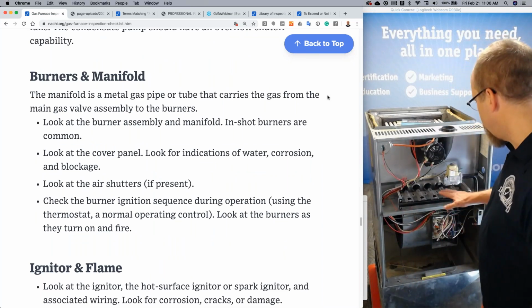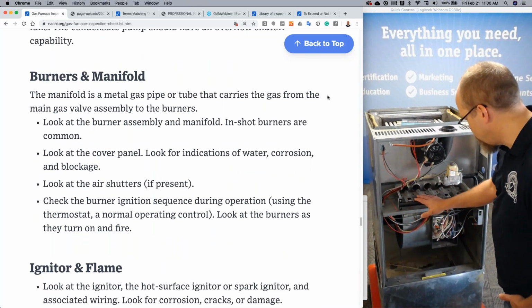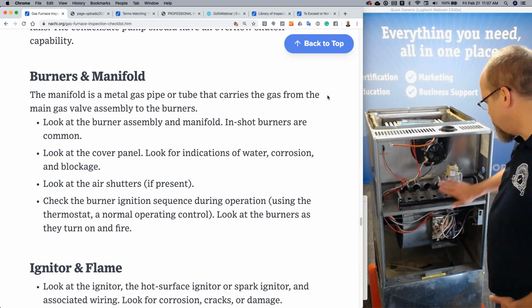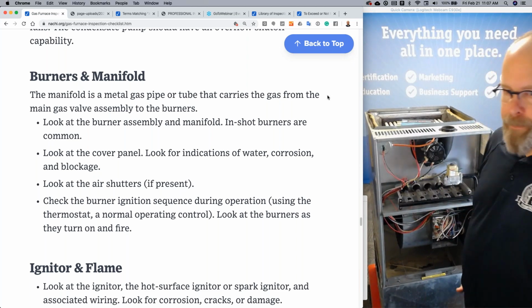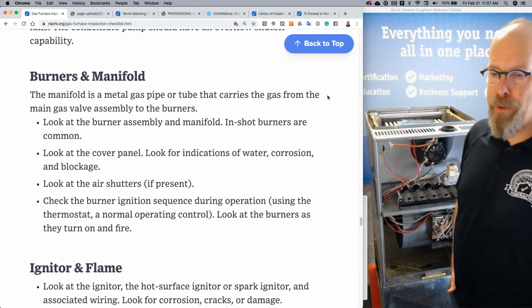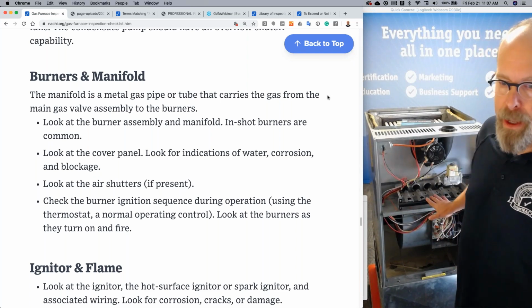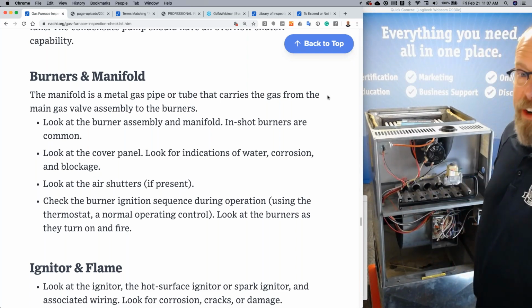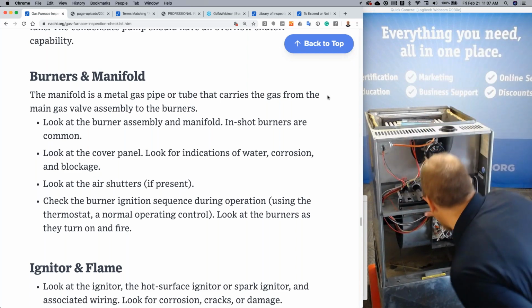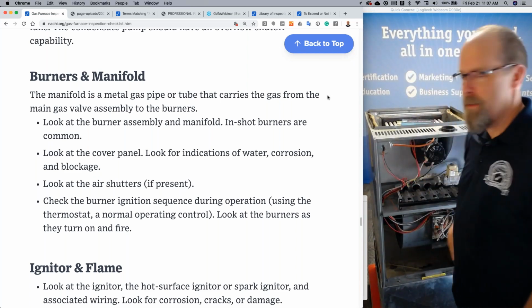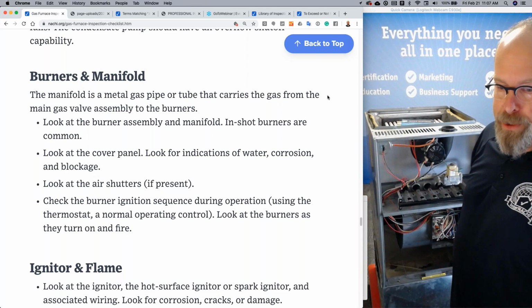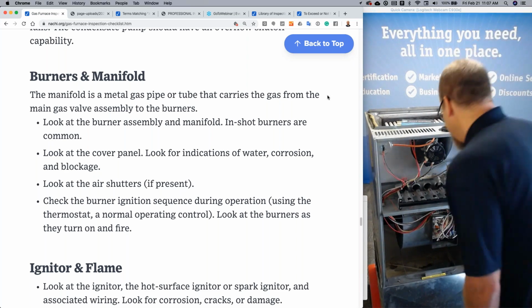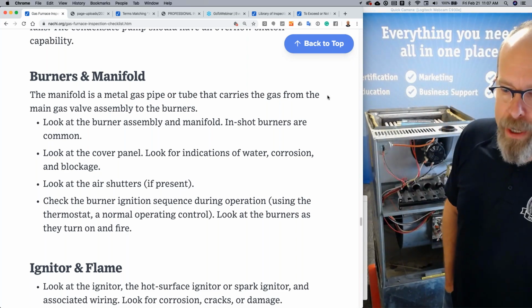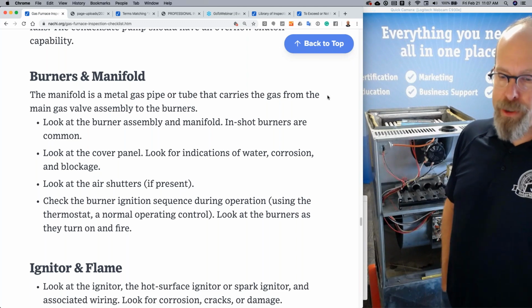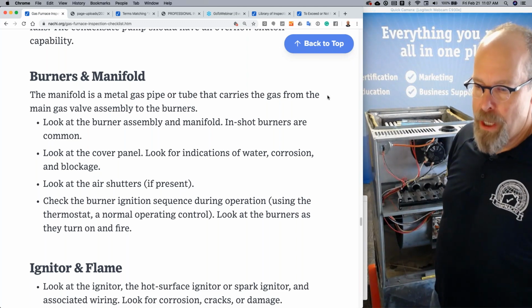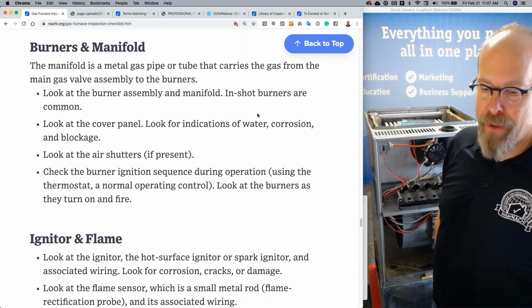Burners and manifold. So there's the burners. This is the gas manifold. This is the gas valve assembly. Look at the burner assembly and manifold. In-shot burners are common. Yep. Look at the cover panel. Look for indications of water, corrosion, and blockage. Okay. Look at the air shutters, if present. Look at the burner ignition sequence during operation using a thermostat, a normal operating control. Look at the burners as they turn on and fire.